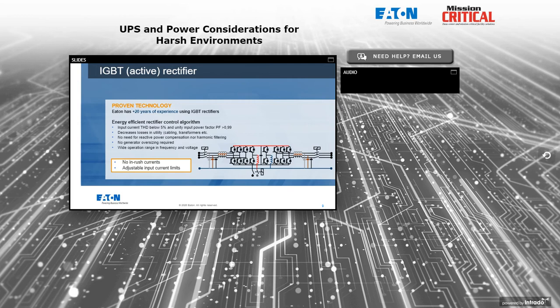So we talked a little bit about the heavy-duty rectifier. Nowadays, UPSs use active rectifiers instead of diode or SCR type connections, and the input THD is controlled to be less than 5%, with the input power factor near unity, about 0.99. So this decreases losses in utility cabling and transformers. There's no need for reactive power compensation or harmonic filtering on the front end of the UPS, which improves reliability, reduces cost, and slightly improves efficiency. It generally eliminates the need for greatly oversizing the generator. That doesn't mean the generator doesn't need to be a little bit bigger than the UPS, at least 1.25 to 1.5 times the size of the input capacity of the UPS.